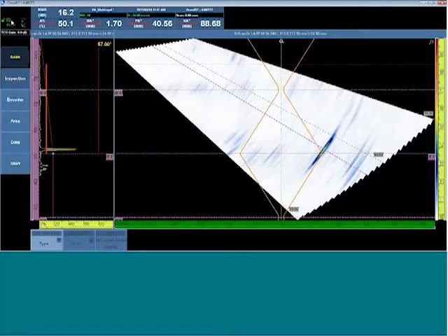And once that happens, the pulsar is now married to the speed of the scanner up to the maximum scan limit, which in this case was a PRF of 50 millimeters per second. The software will record every focal law or A scan on every group at the inspection resolution entered.